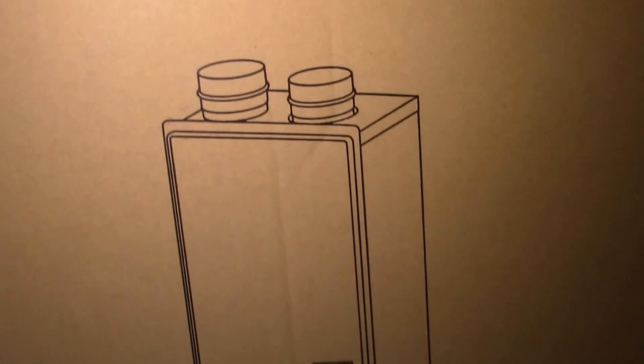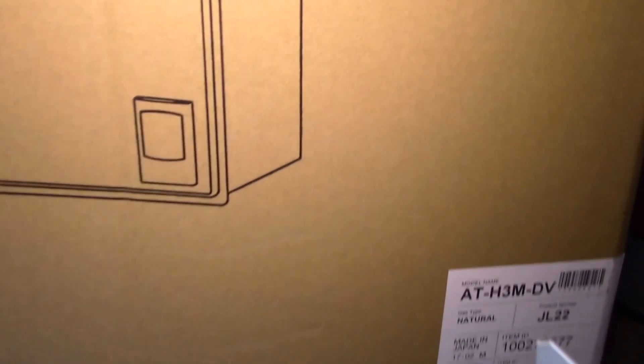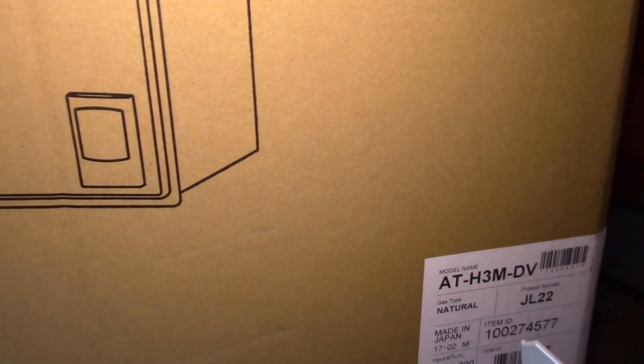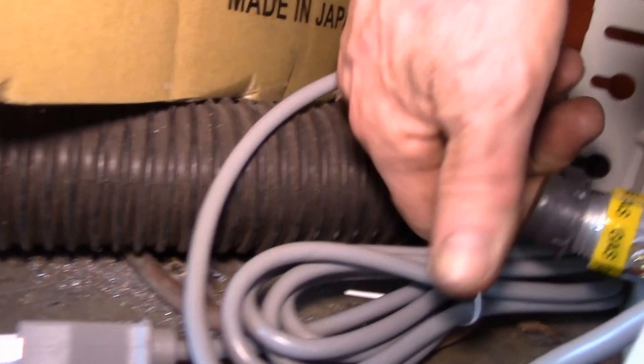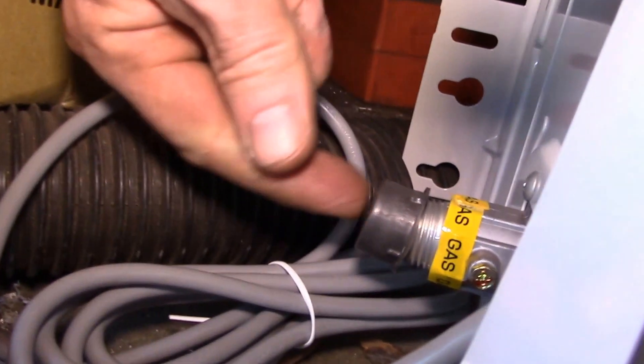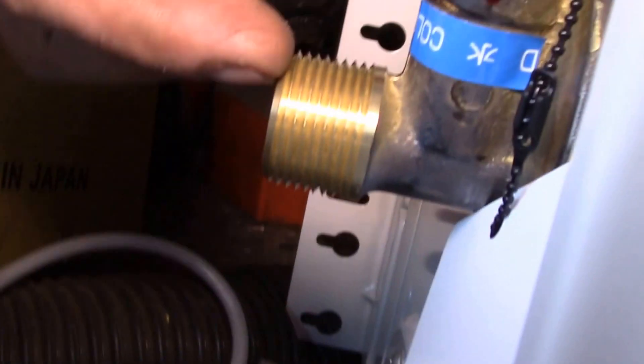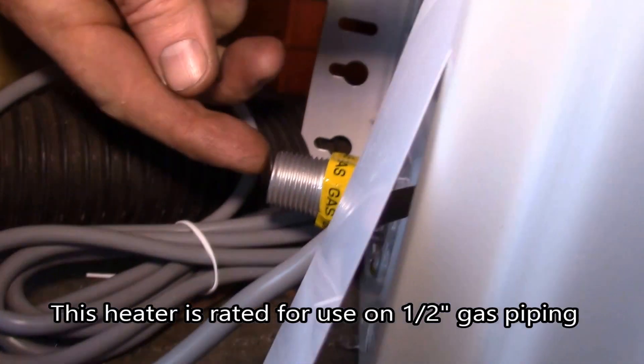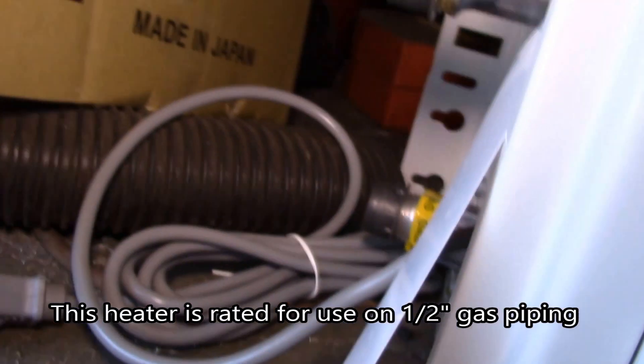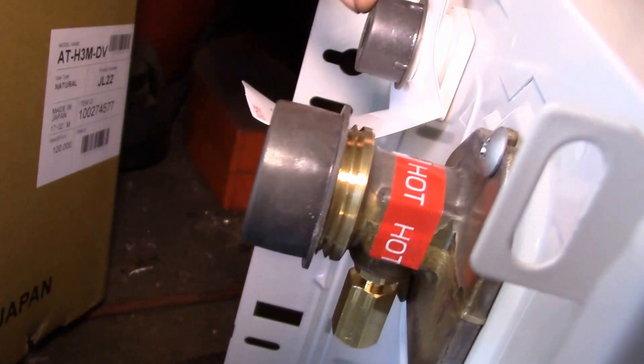And it should have, yeah there we go, this one does have the half inch pipe thread. There's your three-quarter inch on the water and half inch on the gas. So that's the unit I wanted. And then there's your half inch condensate drain right there, three-quarter on the hot and the cold, half on the gas.